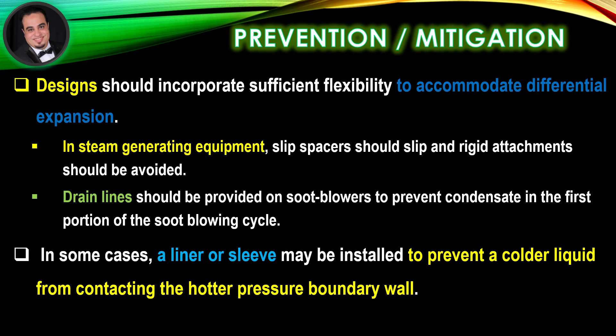Drain lines should be provided on soot blowers to prevent condensate in the first portion of the soot blowing cycle. In some cases, a liner or sleeve may be installed to prevent a colder liquid from contacting the hotter pressure boundary wall.